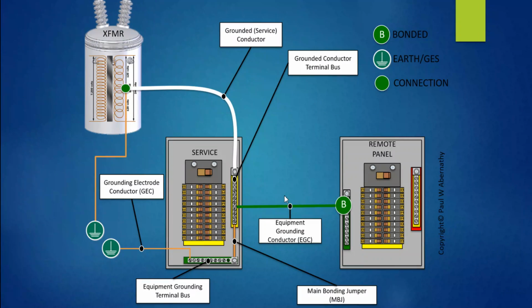Here's the one. Remember I talked to you earlier about the option to have the two different buses. This is the one they connect to the enclosure using the actual screws in a little kit that's provided with this enclosure from the manufacturer. They make that connection, and then you have to connect it over to the grounded terminal bus, and they do that through a main bonding jumper. Now, if this is the choice and it's a wire type main bonding jumper, then they're going to have to size this, and we'll talk about that in a second. Ultimately, it's going to lead us to 250.102(C)(1) for sizing this, but that's the configuration they'll do. Everything else down here didn't change. It's simply showing you two options for two types of configurations.